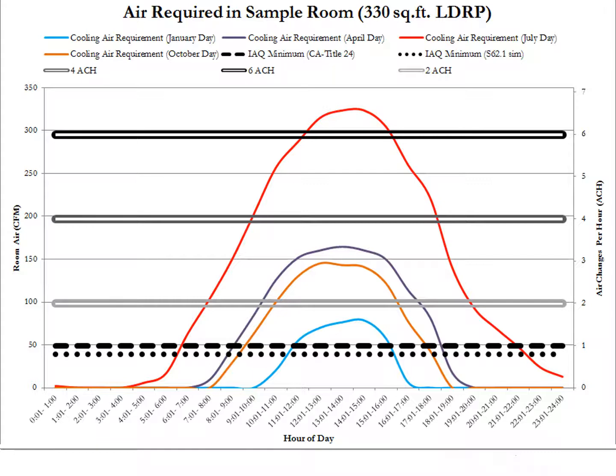Now, California says that if you use 100% outside air, the minimum ventilation rate is 2 air changes per hour—that's the gray line down at the bottom. But the national standard 170 says minimum ventilation is 6 air changes per hour, 24/7. That's the line at the top of the page.